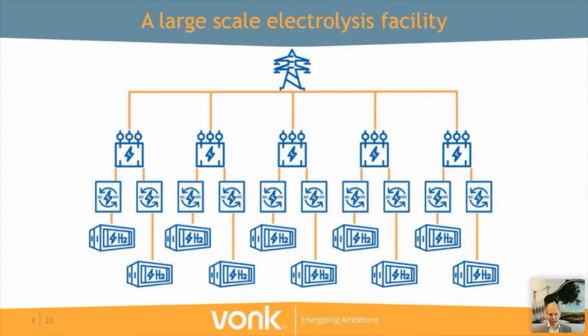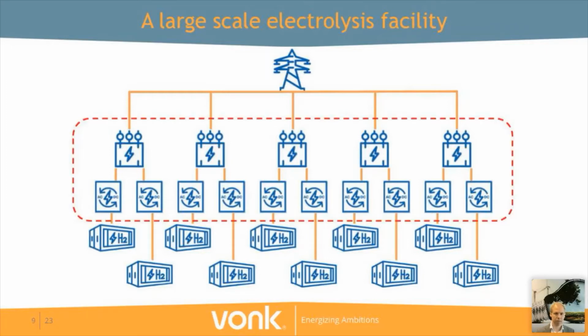To give you a better perspective on how we are approaching this subject, we've got this graphic. We're looking at the facilities as they are set up today, and in most of the cases, you can see this as displayed here. We're looking at facilities with power levels of tens of megawatts up to several hundreds of megawatts. These are often set up with a connection to a high voltage AC grid, as you can see at the top of your screen. Then this is converted to medium voltage AC, and then there are several building blocks in place consisting of a transformer, rectifier, and electrolysis units. Within this webinar, we will focus on the transformer rectifier combination, which we sum up as the power supply.